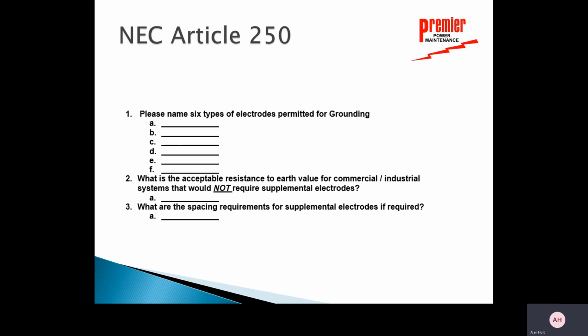So question number one. Please name 6 types of electrodes permitted for grounding, according to Article 250 of the National Electric Code. So let me look at this. I can have a metal underground water pipe. Just as a side note, it doesn't really do good to have a metal underground water pipe if you've got PVC inside the house that meets up with that. That's a problem. You can have metal in-ground support structures.